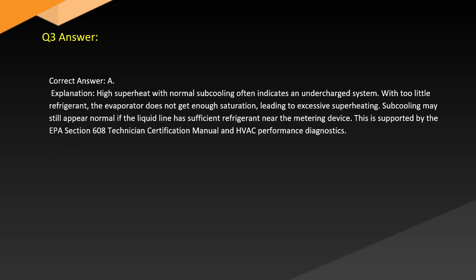Answer. Correct answer: A. Explanation. High superheat with normal subcooling often indicates an undercharged system. With too little refrigerant, the evaporator does not get enough saturation, leading to excessive superheating. Subcooling may still appear normal if the liquid line has sufficient refrigerant near the metering device. This is supported by the EPA Section 608 Technician Certification Manual and HVAC Performance Diagnostics.